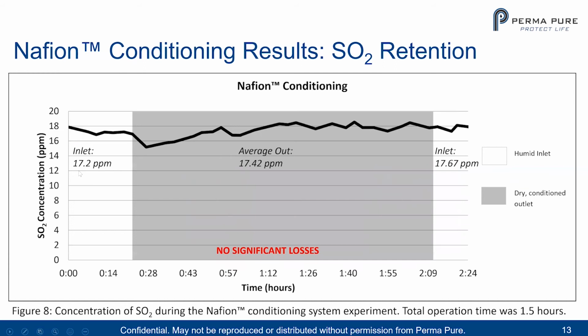So let's take a look at our Nafion conditioning results with SO2 retention. Our inlet here was 17.2 parts per million. And when we went through the dryer, our average was 17.42. And then when we turned back to the original gas, we were up at 17.67 parts per million. So you can see there's really no significant losses from using the Nafion dryer to dry that sample gas. That's a significant difference. No losses versus 30 to 40% loss.